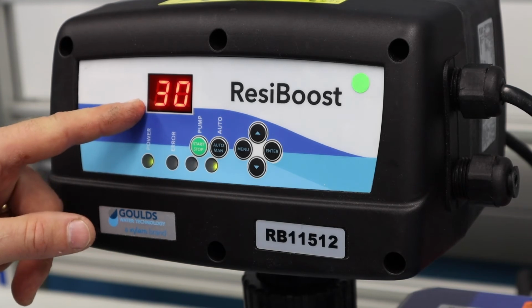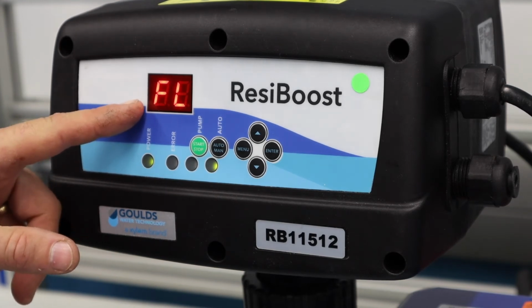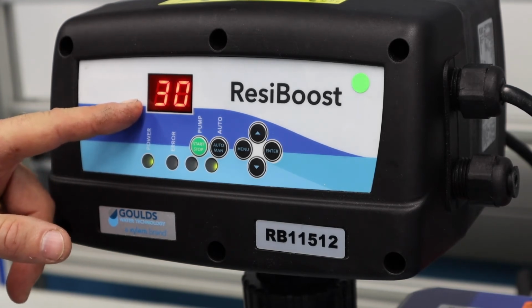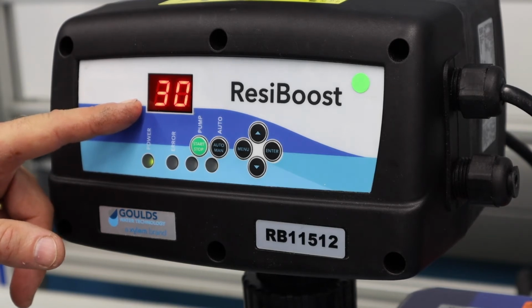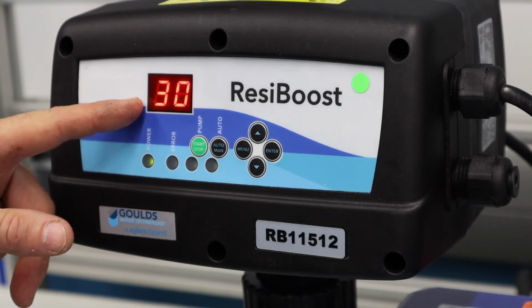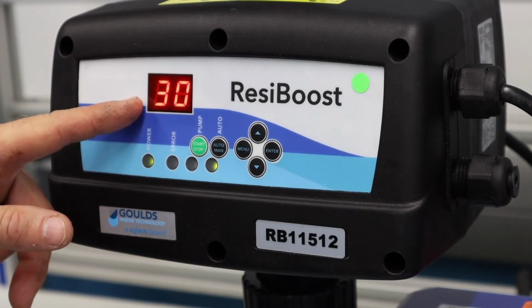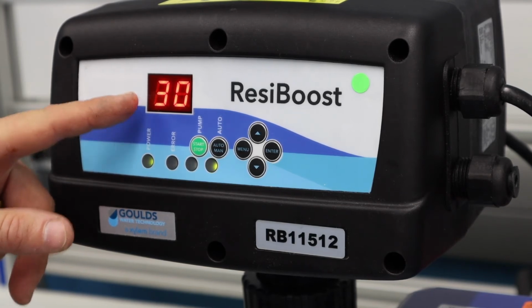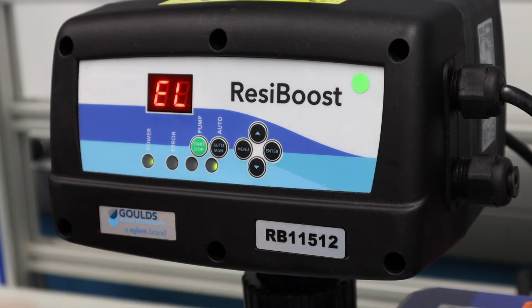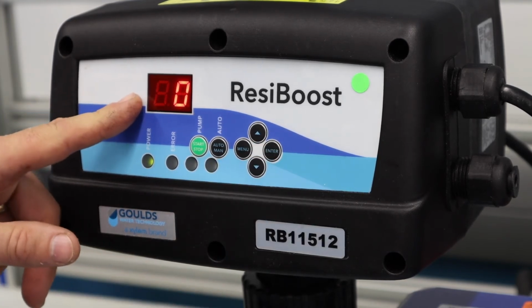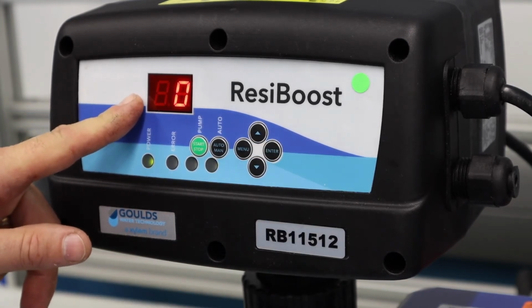Next parameter is FL, min frequency. And that's preset to 30. And that's pretty common for most VFD systems. And that's the point at which it's going to turn off. And we do not want most systems to go below 30. So we're going to leave that. And that's in hertz.